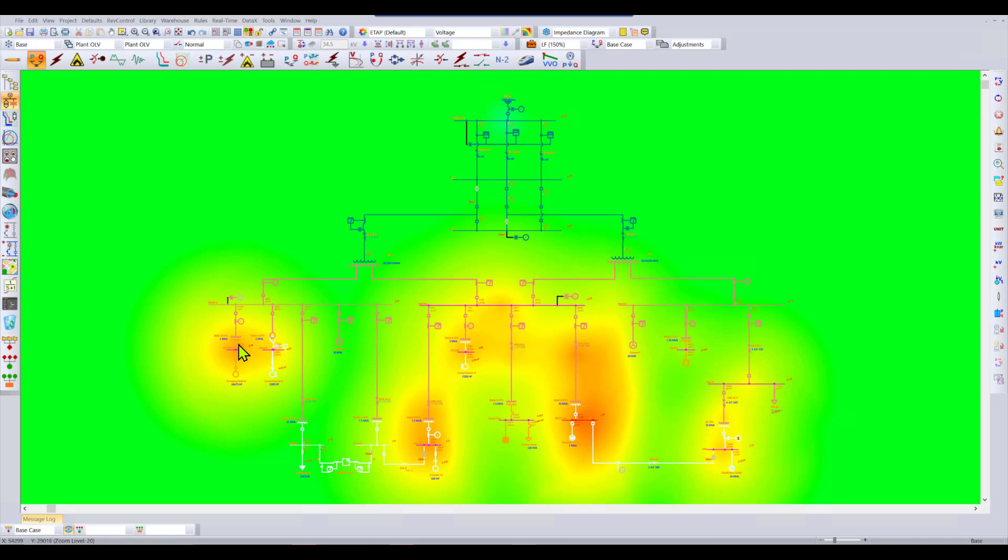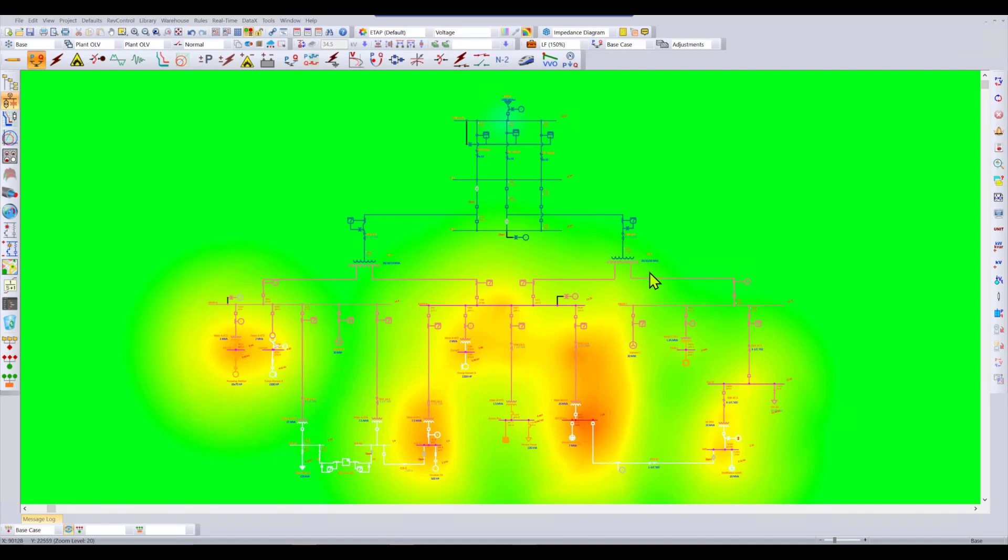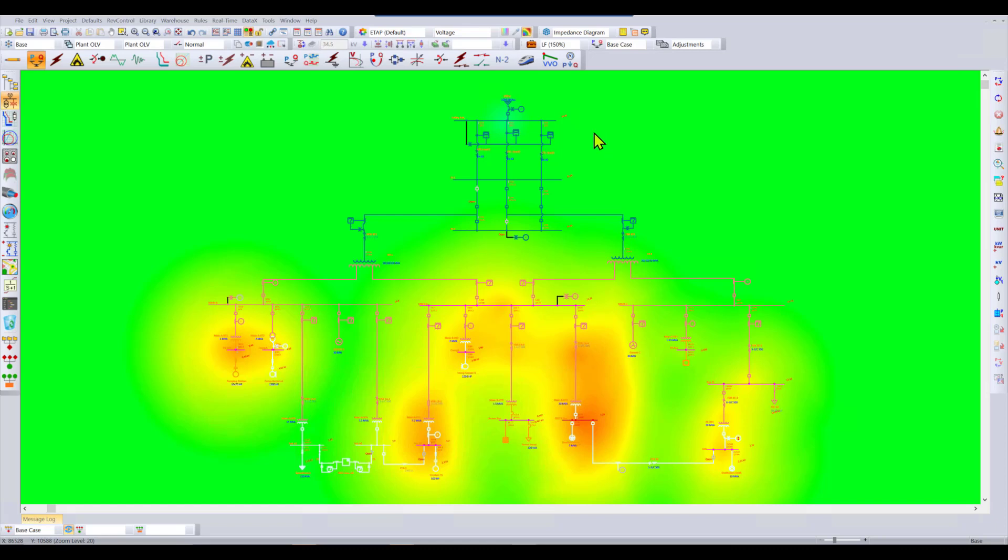The orange and red patches are essentially telling us where we have lower voltages in the system. The green area, everything is perfectly fine, meaning it's close to nominal values. If you see any of the blue colors or bluish colors, those are areas where we can see slightly over voltage but not by much. In this case, this is our base case that we are running through load flow.